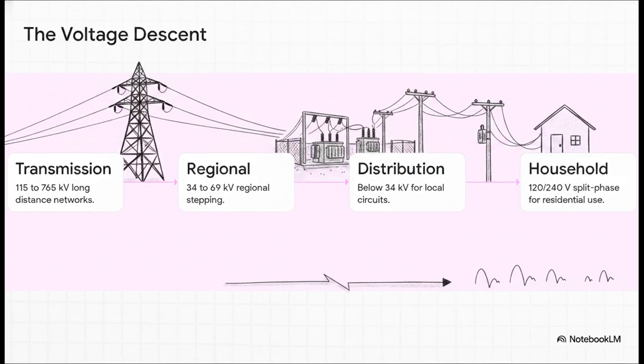First, regional substations drop those extreme highway voltages down to sub-transmission levels, usually around 34 to 69 kilovolts. Then, local distribution substations step it down again to primary distribution circuits, typically around 7,200 volts, which is exactly the voltage running through the lines you see on the wooden poles in your own neighborhood.